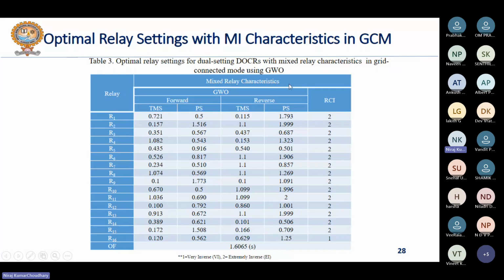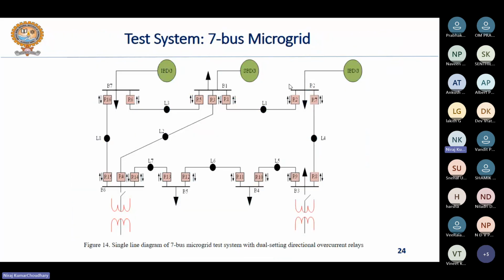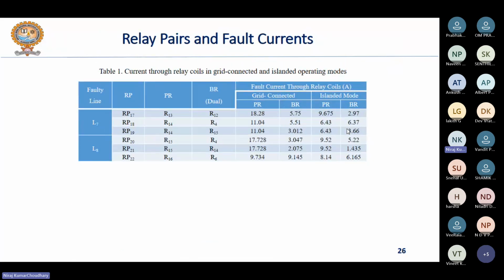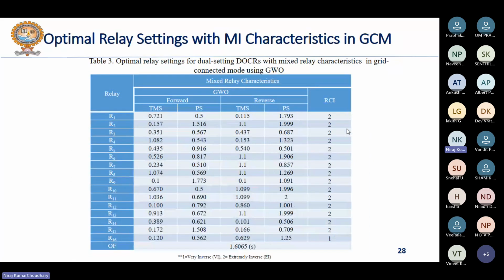When mixed type of relays are used in the system, suppose in our system that we have considered, in this figure 14, you have different number of relays connected to the system. Suppose you have 16 relays here connected to the system from R1 to R16. So in case of mixed inverse characteristics, it may be possible that relay R1 is a very inverse type relay, relay 6 is a normal inverse type relay, and another one, R13, is an extremely inverse type relay. So all it depends upon the calculation of optimal relay characteristics through this relay characteristics identifier.